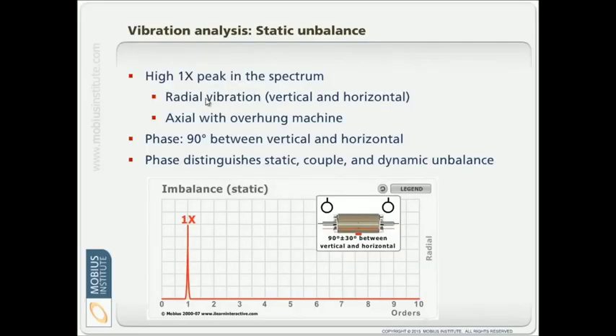So we expect to see the high 1x peak in the spectrum. We see the 90 degree phase relationship between the vertical and horizontal. We would expect to see very little phase difference when comparing the vibration readings at each end of the rotor, and we expect to see the bulk of the vibration in the radial or vertical and horizontal direction and very little axial.